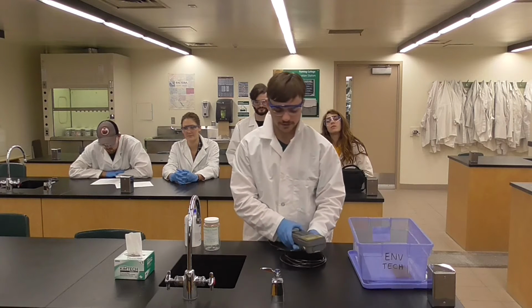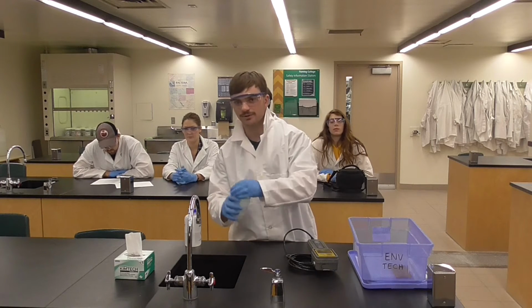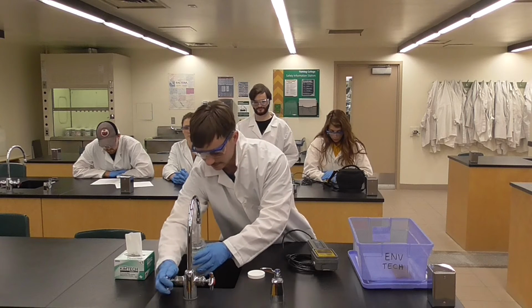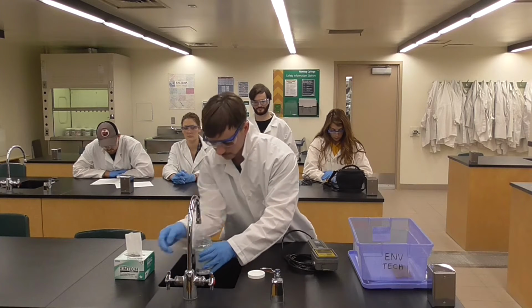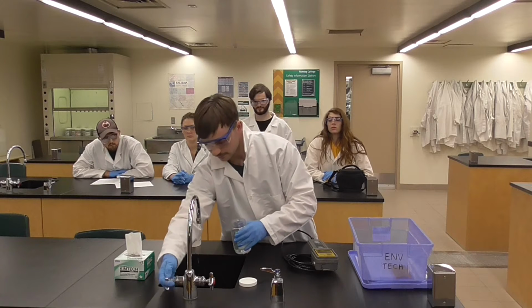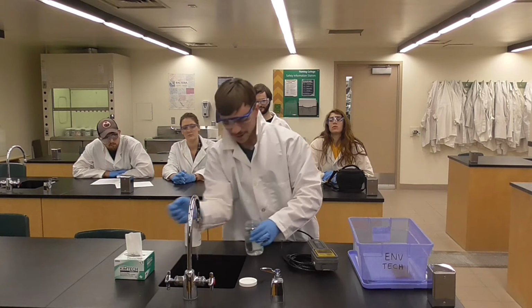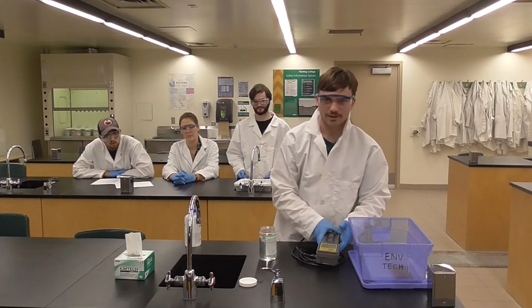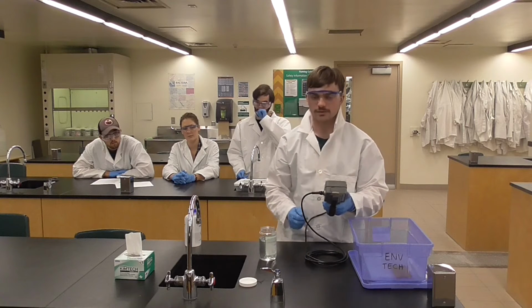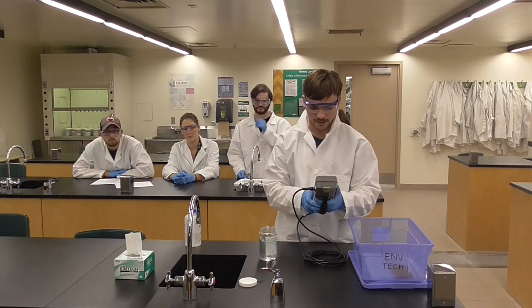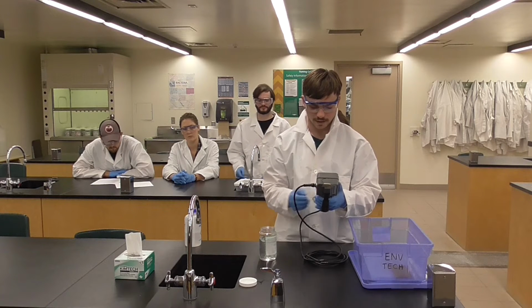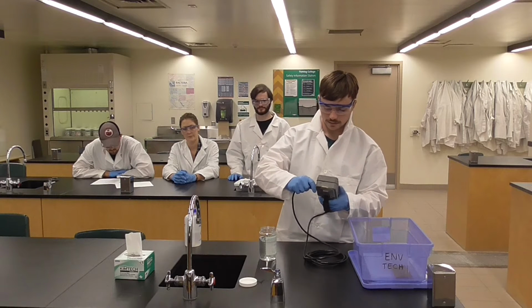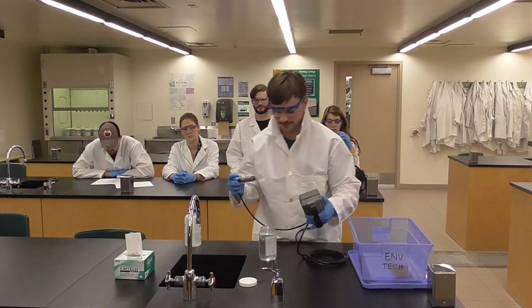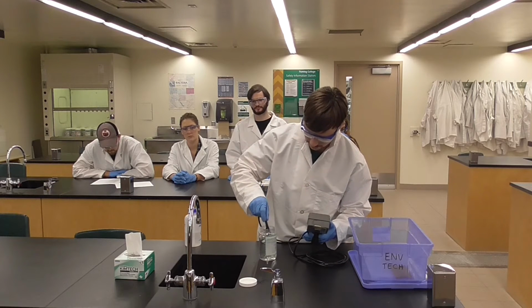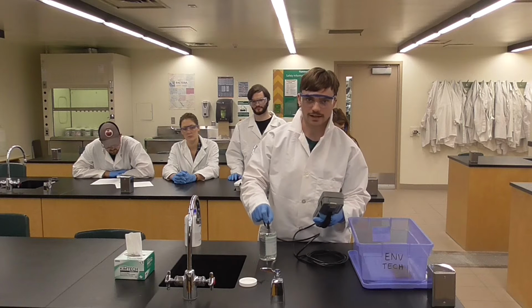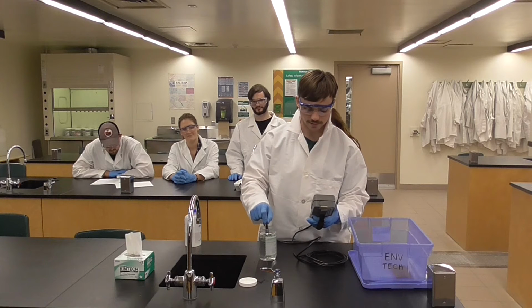So now I'm going to collect my water sample from the tap. Alright. Now that I have my water sample, I'm first going to measure conductivity. So I will press mode and get back to conductivity. I will now dip the probe into the sample and bob it up and down until I have a stable conductivity reading.